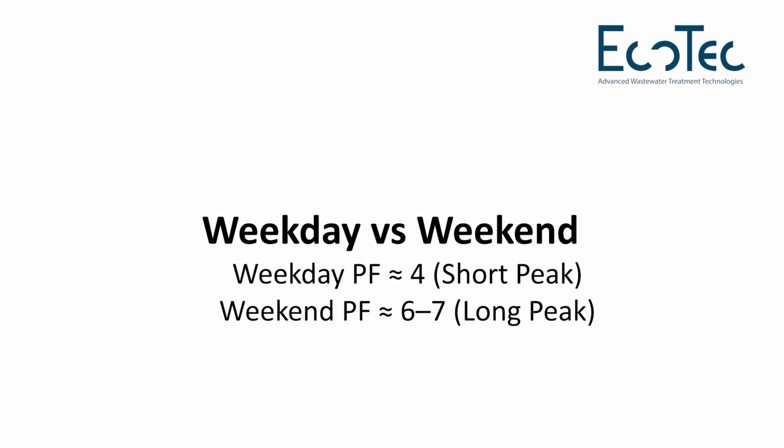There's more to this. A peak factor of 3 over 12 hours is applicable on a weekday. But think about weekends. Weekends, every mall gets its footfall completely differently. There are more people coming and there are more surges. So the peak factor can go up to 7. So you see the big difference here.